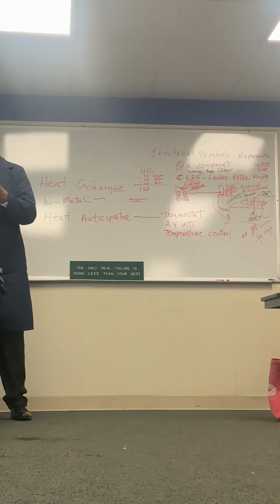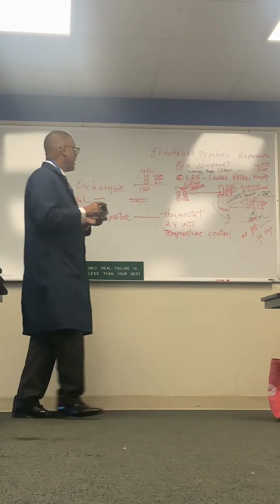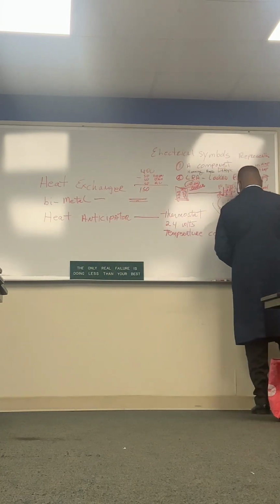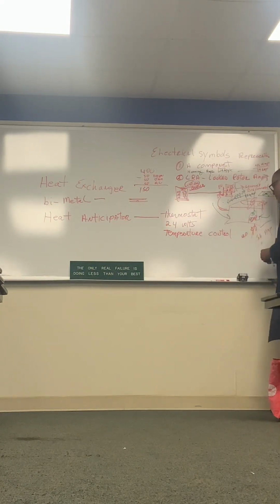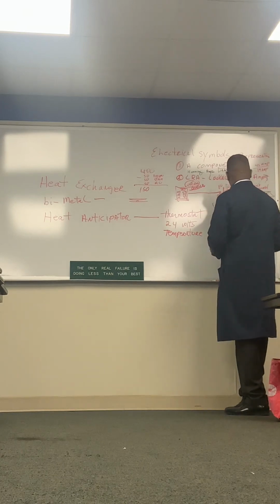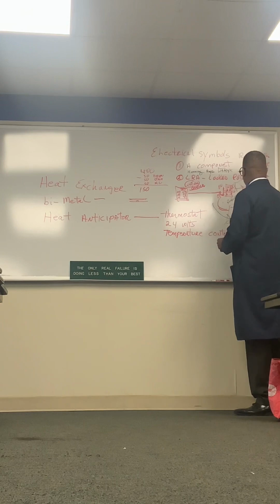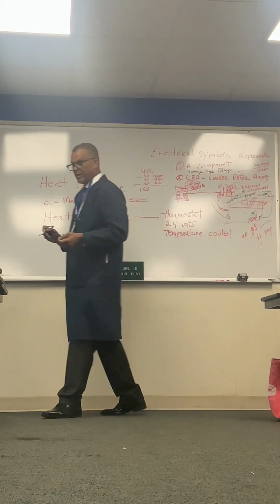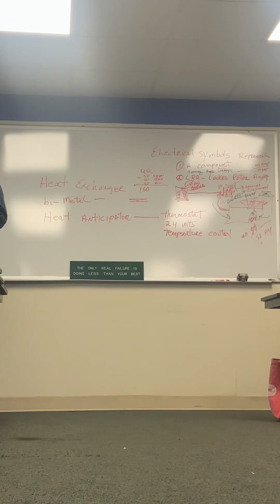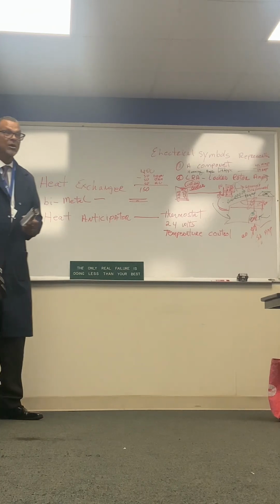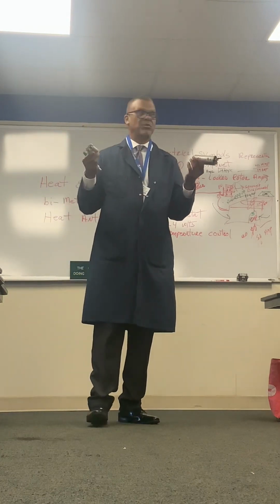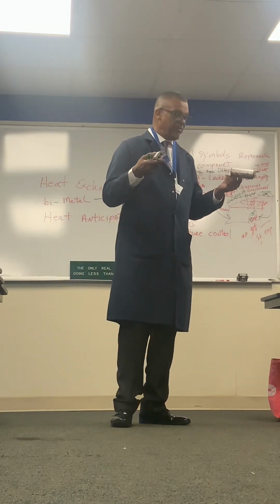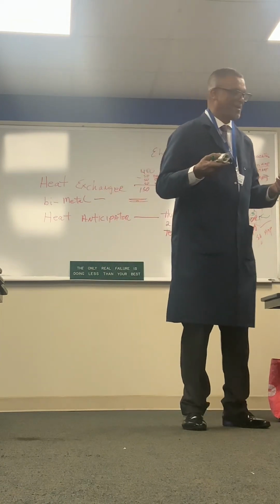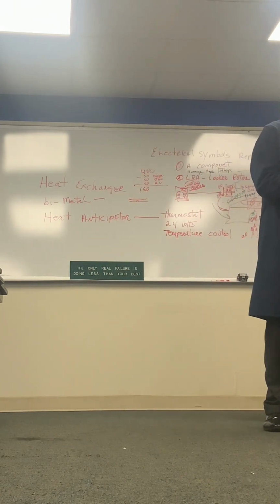And so you have L1 and L2 coming off here with 240, and then when you close to T1 and T2, 240 comes this way. So if I have my contactor with L1 and L2, then, question? What question? Does that go through the capacitor first? It actually does. I was coming right over here. There are 2 different types of capacitors. What is the difference between these 2 types? One starts. Give me some answers. One starts. What's the difference? Just look at it, at least tell me that difference.